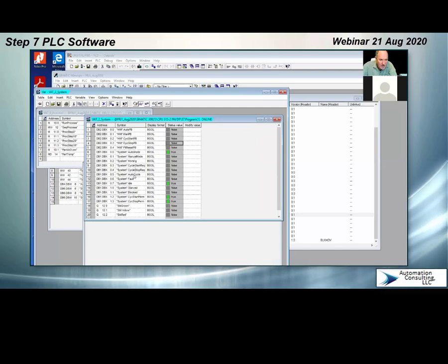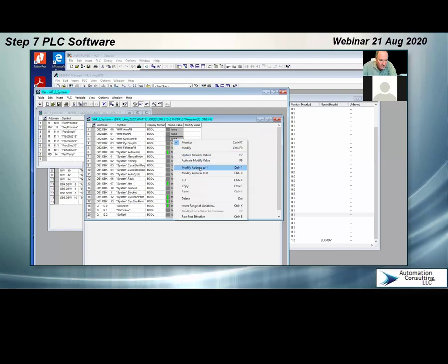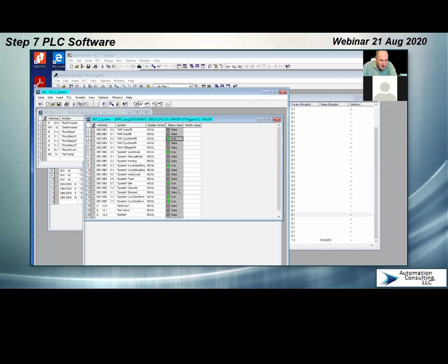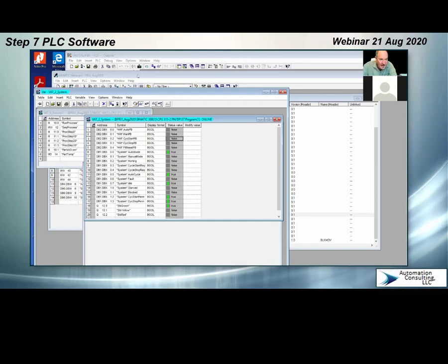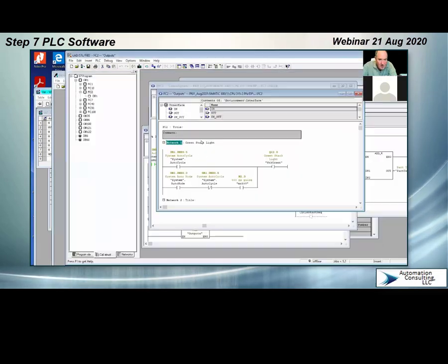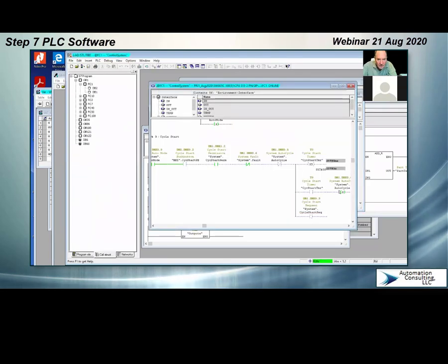A lot of these bits are just bits in that routine. I'm going to go ahead and turn this on. It goes tick, tick, tick, and eventually latches in. And we are now in cycle start. So we'll turn the button back off. And the logic for that again was here in this control system. You see the timer expired, 3-second timer, and I latched in auto cycle.